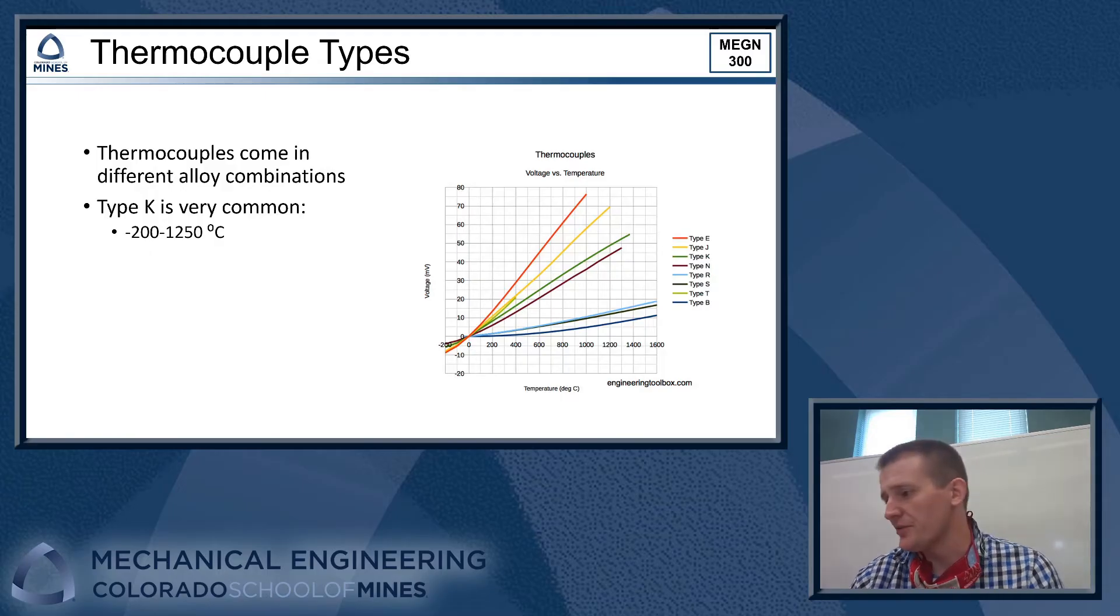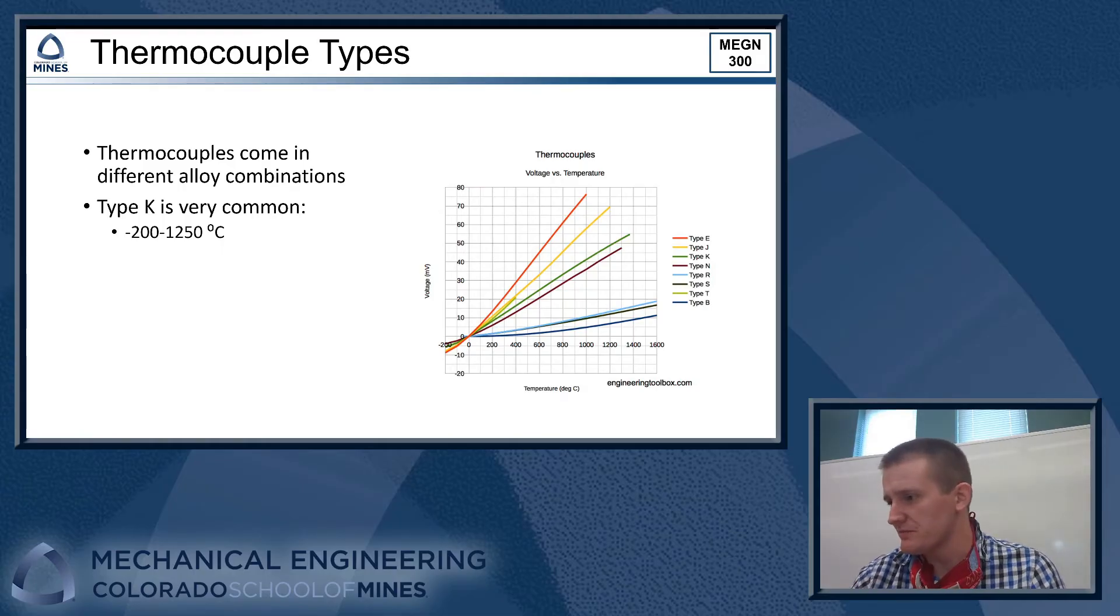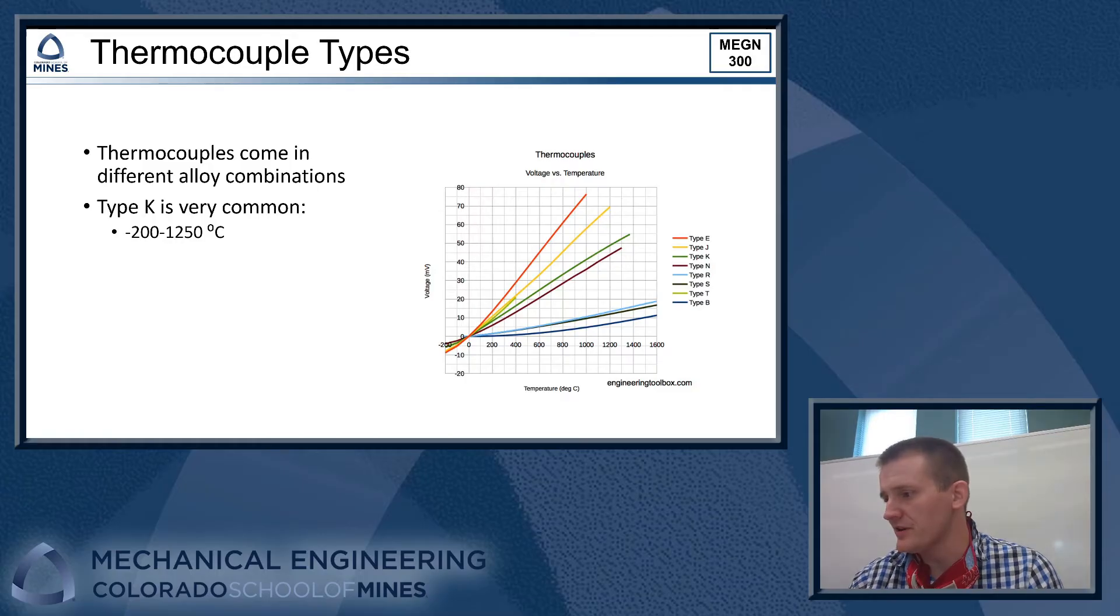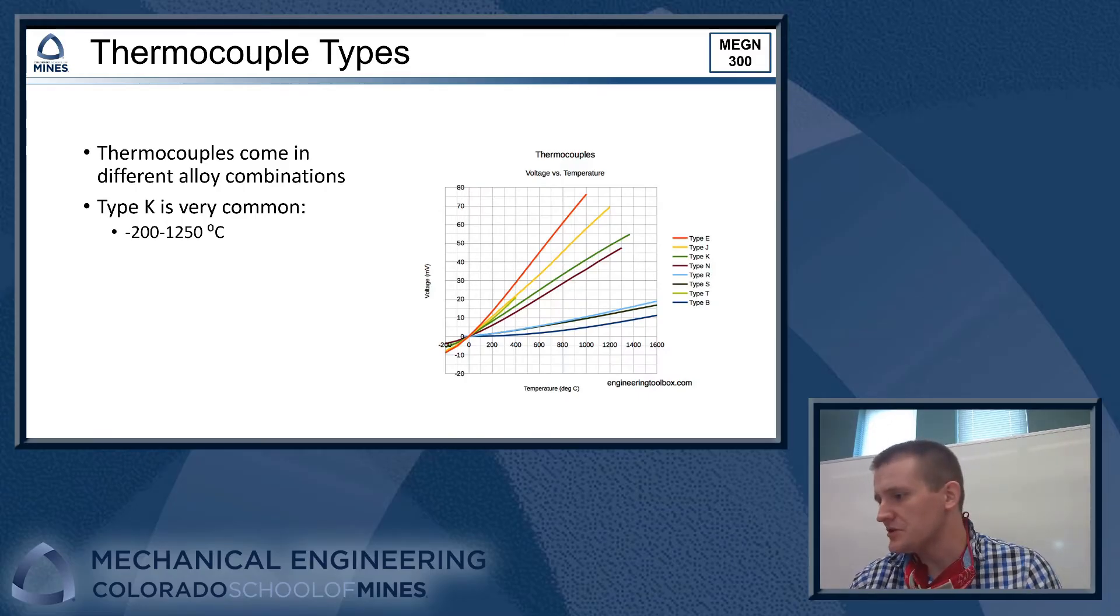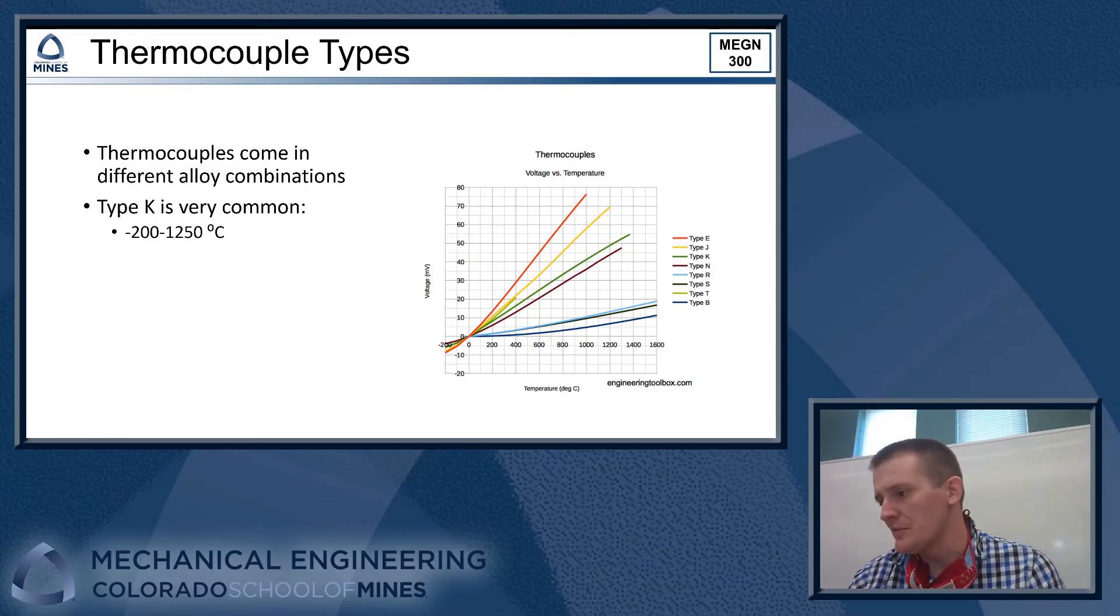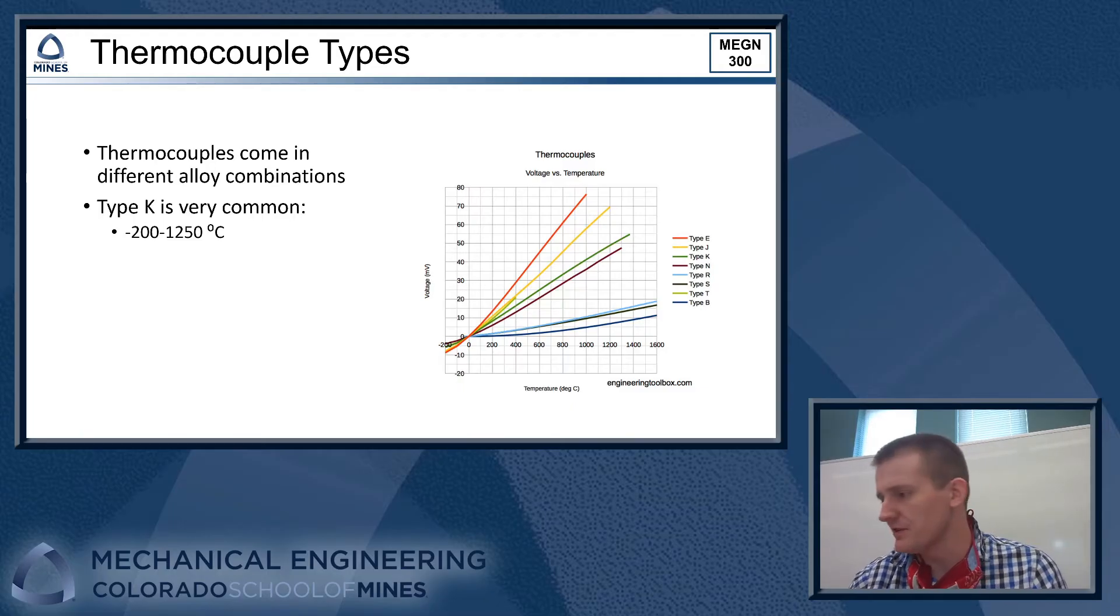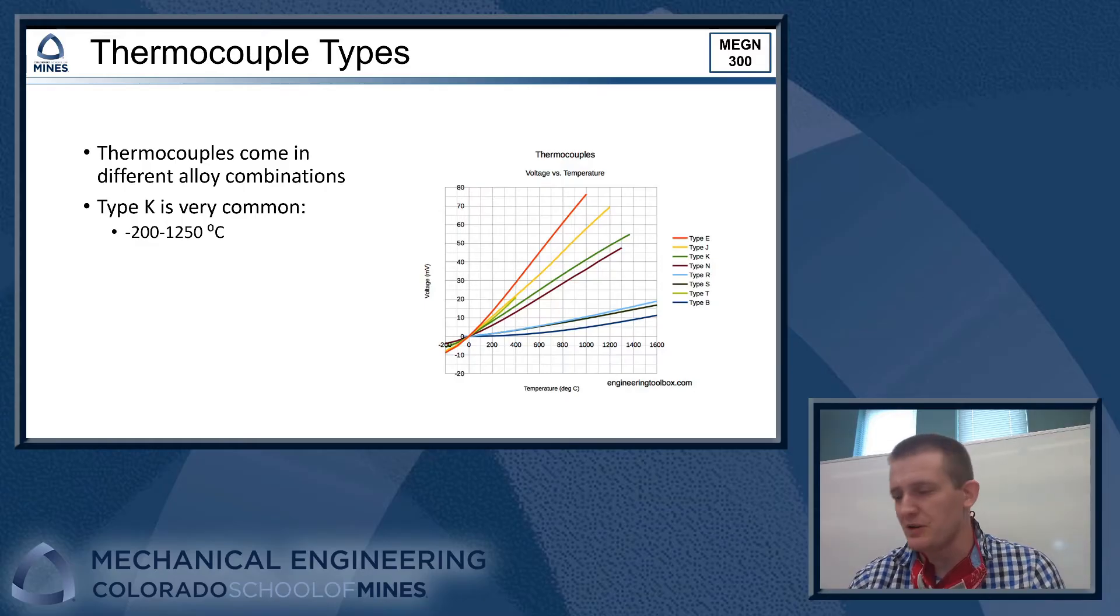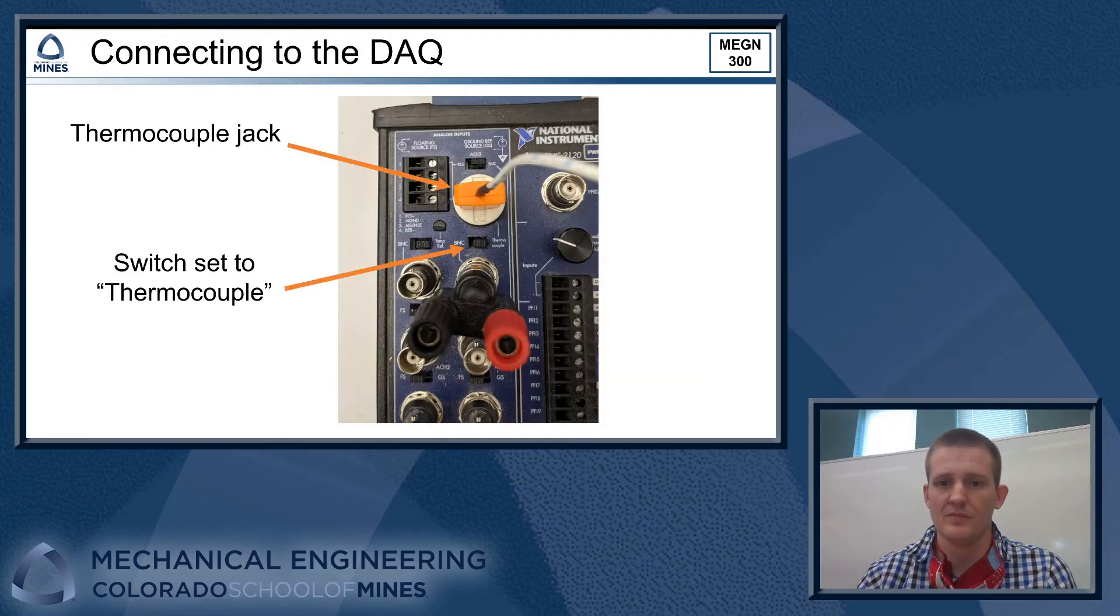Thermocouples come in different flavors or different types. They're all given a special letter, and that would be standard across manufacturers. They all have a different characteristic response to temperature. So their output voltage is going to be a function of temperature, and it's going to be a little bit different for each type of thermocouple. Each of these types is just a different combination of alloys that's inside of the thermocouple, and that's what makes their voltage characteristics different. Probably the most common one that you'll run into and the one that we have in the lab today is called type K. It's fairly inexpensive, and it has a really wide temperature range that it can cover. It'll cover from negative 200 to 1250 C. So that's quite a broad range of temperatures that you can measure with this one device.